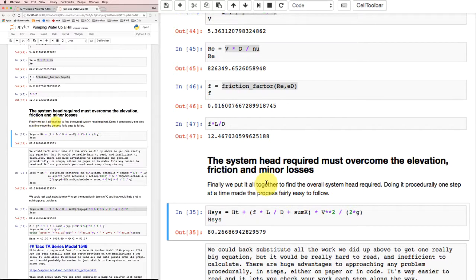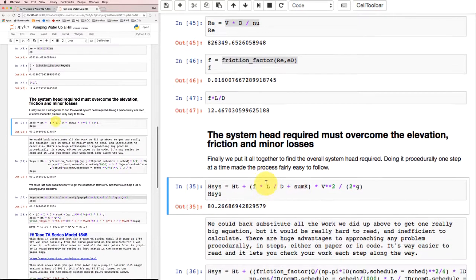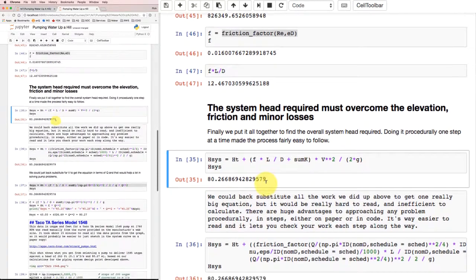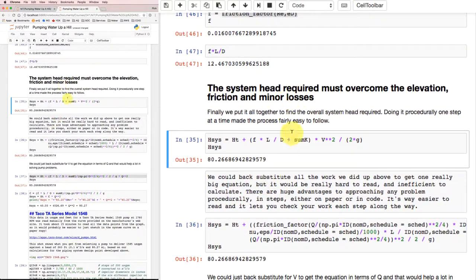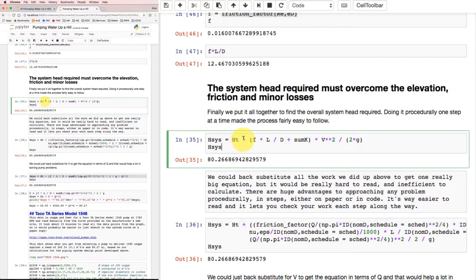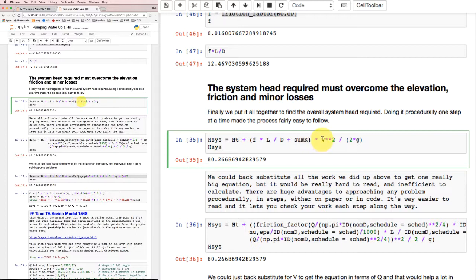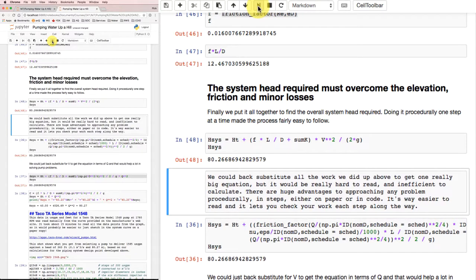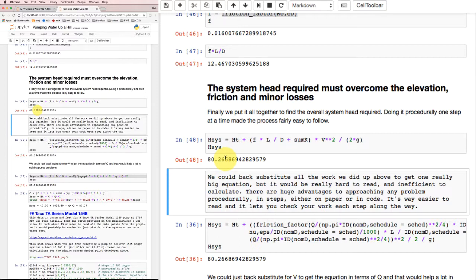The system head required must overcome the elevation, friction, and minor losses. We're going to put it all together. We did it procedurally one step at a time, which makes the process fairly easy. The system head requirement is the head of the tank, how much we need for elevation, plus whatever we lost along the way: fL/D + ΣK times V²/2g. This is just the same equation we had on paper. When I run that, I get 80.27 meters of head rise we're going to need across our pump to satisfy the head requirements of the system.